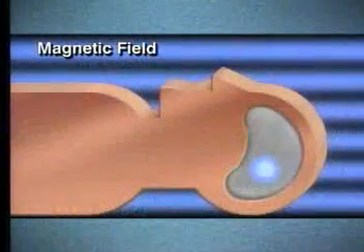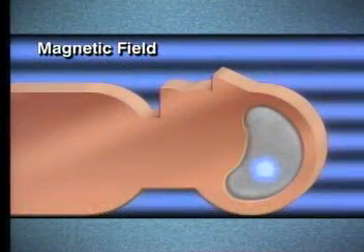Well, first of all, maybe we should look at what MRI stands for. It's magnetic resonance imaging. So obviously we have a magnetic field, we have some resonance happening, and we take pictures. So as far as the magnetic portion is concerned, we have a magnet, and what we use is a superconductive magnet, which is a high field.